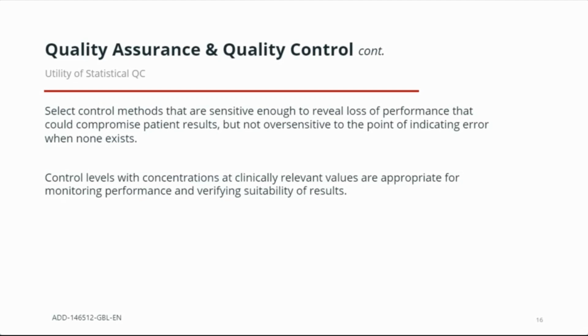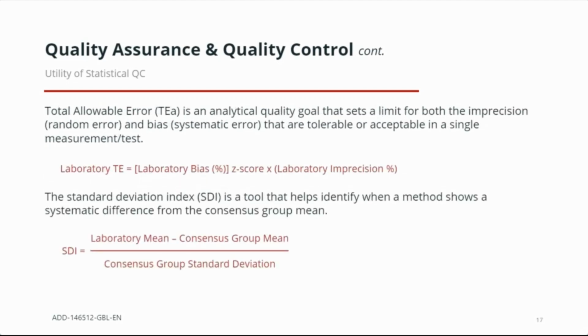So how do we ensure our QC is effective? A number of statistical tools are available. The well-known Westgard multi-rule QC uses a combination of decision criteria rules to help us assess out-of-control situations. We also have total allowable error, which is a quality goal that sets a limit for both the imprecision, which is random error, and bias, which is systematic error, that are tolerable or acceptable in a single measurement. So in that calculation, we take bias, imprecision, and a z-score. It's common industry knowledge to use 1.65. That implies that 95% of our test results will fall within a total error limit in our Gaussian distribution.